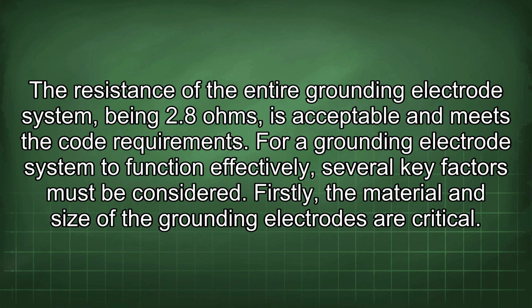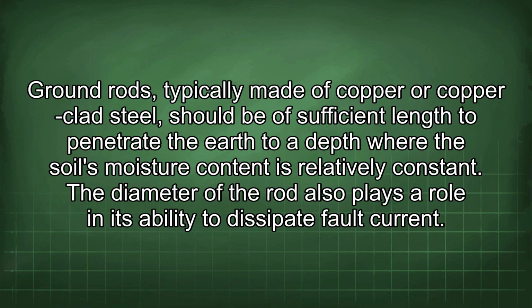For a grounding electrode system to function effectively, several key factors must be considered. Firstly, the material and size of the grounding electrodes are critical. Ground rods, typically made of copper or copper-clad steel, should be of sufficient length to penetrate the earth to a depth where the soil's moisture content is relatively constant. The diameter of the rod also plays a role in its ability to dissipate fault current.